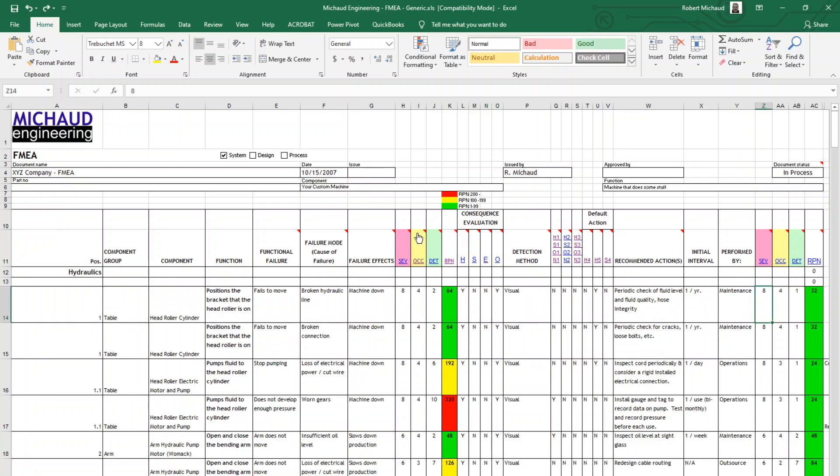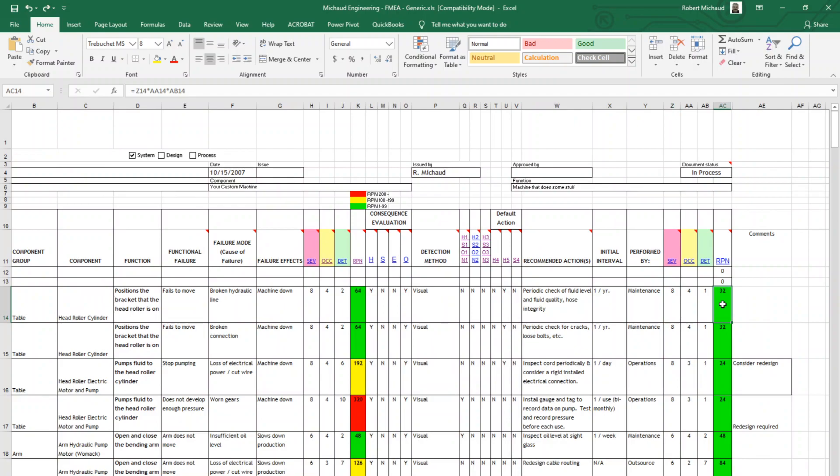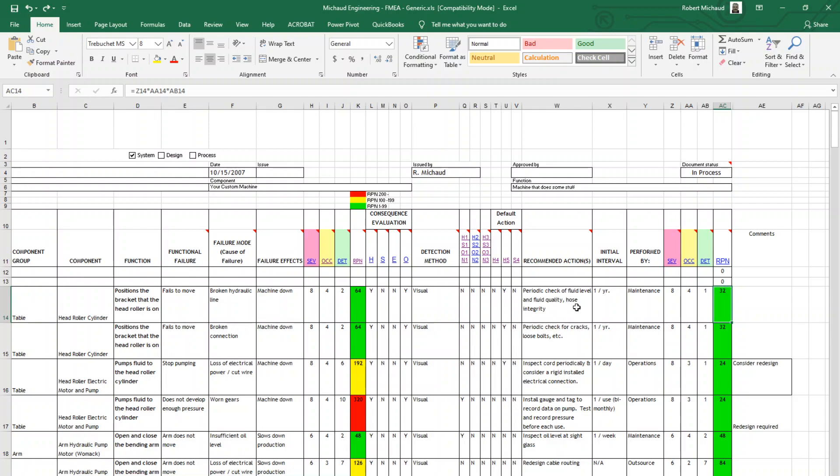Now we're going to go back and we're going to take the same criteria that we looked at over here, and we're going to reevaluate the severity, occurrence, and detection after we've done these tasks. So in other words, if we've accomplished these recommended actions, and we come back to look at these criteria again, what's changed? Have we reduced the severity of it? Have we reduced the chance of the occurrence? Have we changed the level of detection in any way? And now we're going to get a new score here. So by comparing this score to this score, we hopefully have reduced this number and made this less of a problem by virtue of the actions that we've taken.